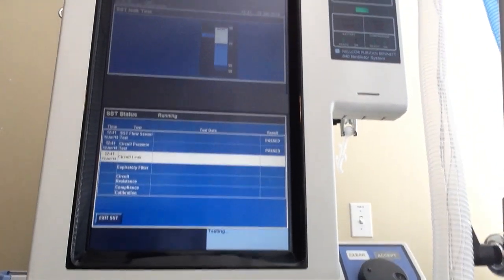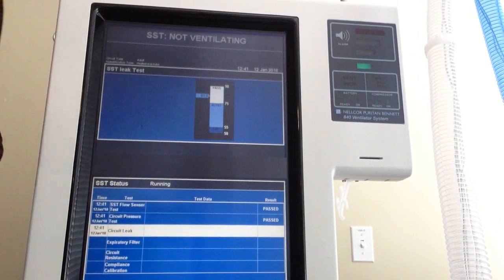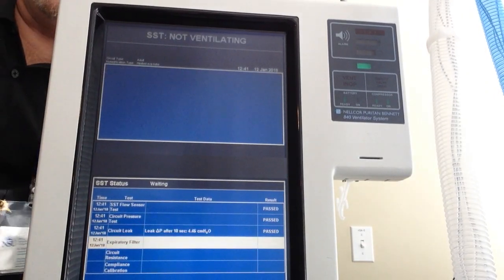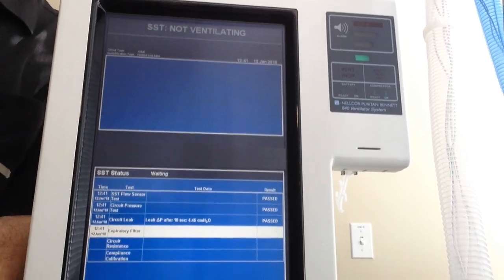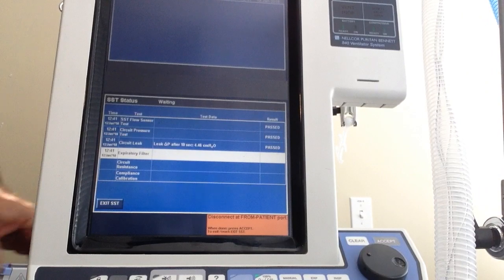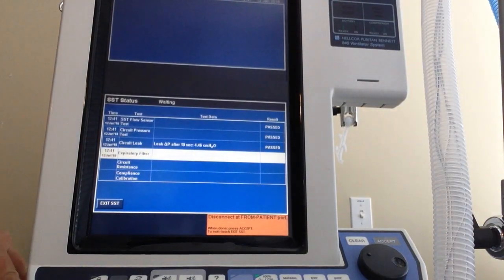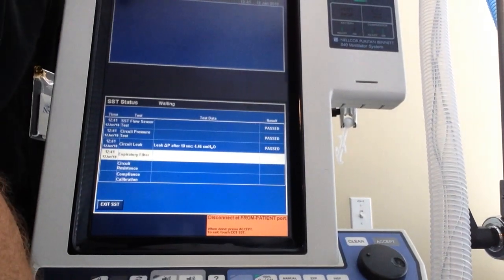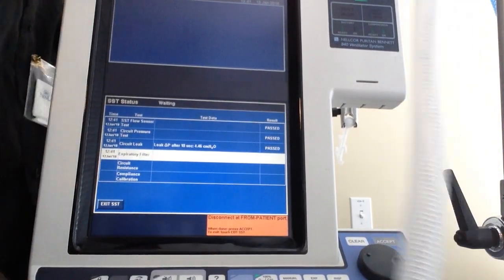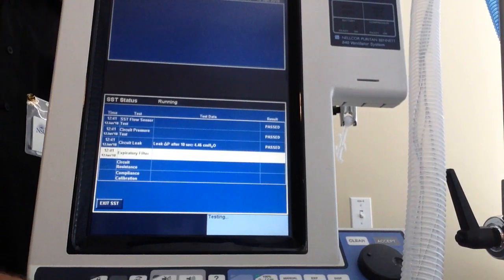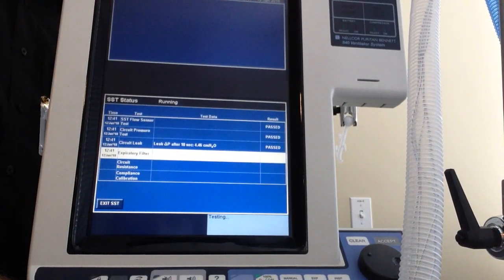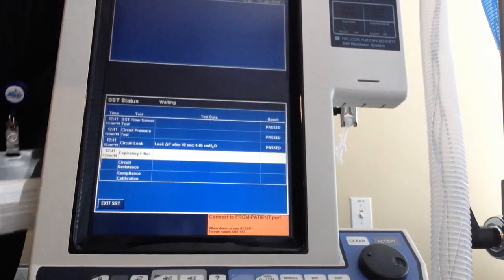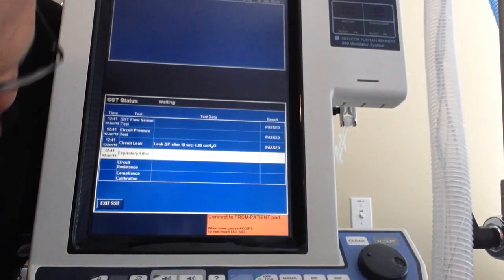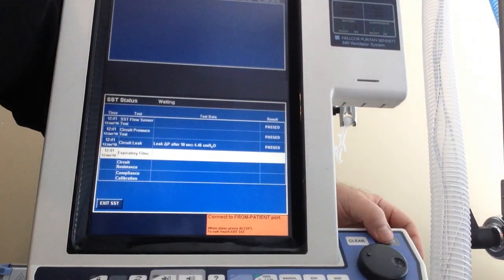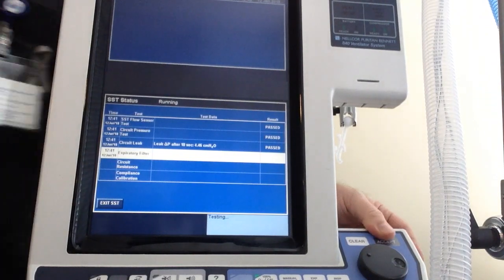Okay, it's doing the circuit test. As you can see here, it's holding pressure. There. So then the next item is disconnect from patient port. So that is my exhalation filter. So I'm disconnecting the expiratory side. Right here, I disconnected it from the filter and I hit accept. Then it tells me to reconnect it. Connect from patient port. I hit accept.